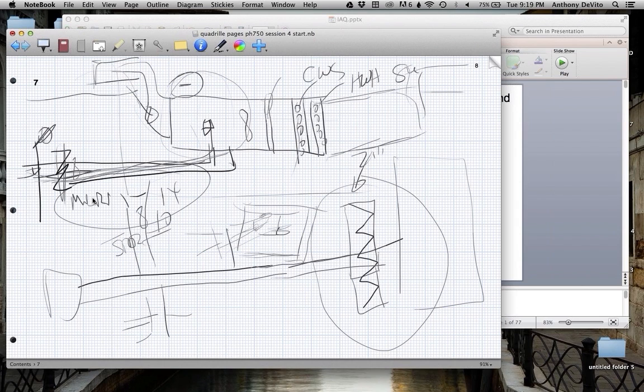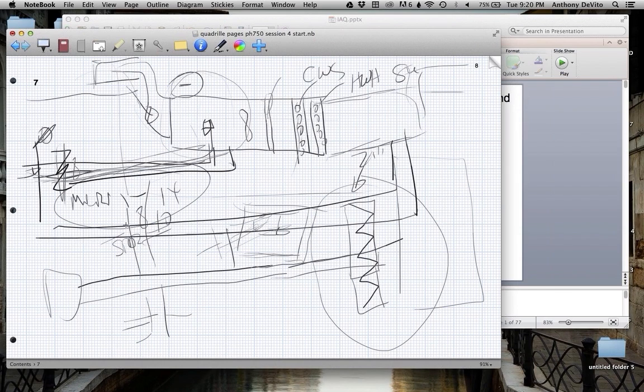So they don't bother to do anything beyond supply that fresh outside air duct. Many buildings don't have enough exhausts, enough losses inside the building to account for that. So on the pressure side, they'll have a duct that goes outside and discharges air at the same rate that you're making it up with fresh air. A lot of times this is called a fresh air intake, and this is called a spill, because you're spilling air out to make up for the fresh air you're pulling in.